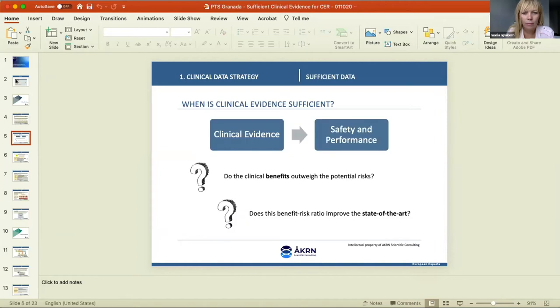So, when is clinical evidence sufficient? You need to demonstrate the safety and the performance, tying back to the previous definitions. The clinical benefits need to outweigh the potential risks. In the MDR, compared to previously under the MDD, there's a very strong focus now on the risk-benefit analysis being more and more important. This is part of your clinical evaluation plan, part of generating your entire technical file, and part of designing clinical investigations and clinical trials.